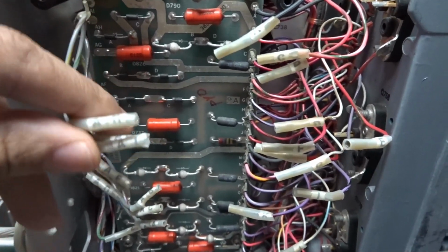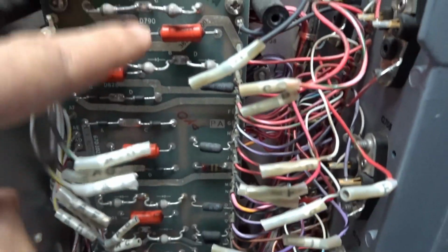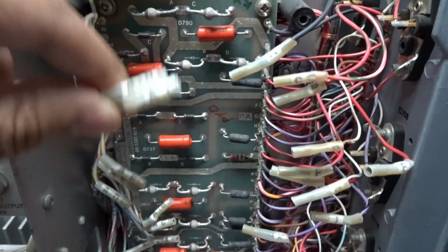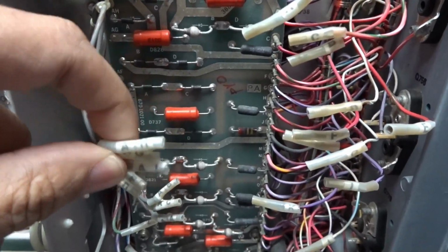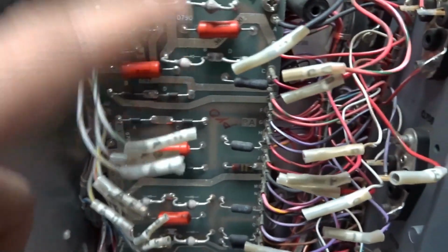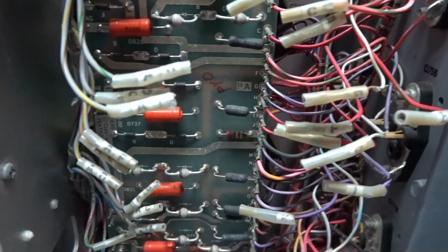Now what I'm going to do is, these are from the transformers, and this is the rectifier board. First of all, I will check the output of the transformer to make sure the transformer is okay. Then after, I will check the rectifier and see if this rectifier board is okay or not.